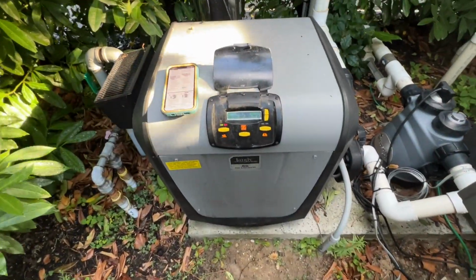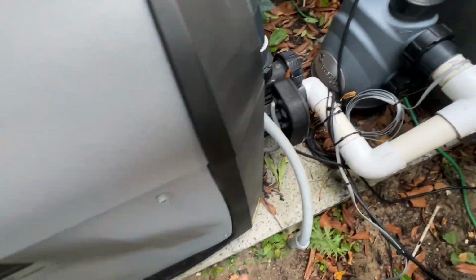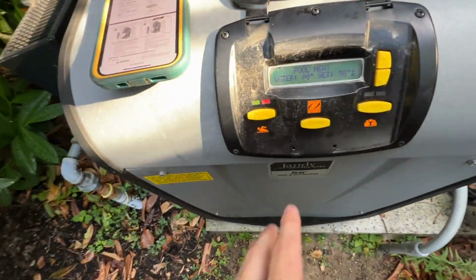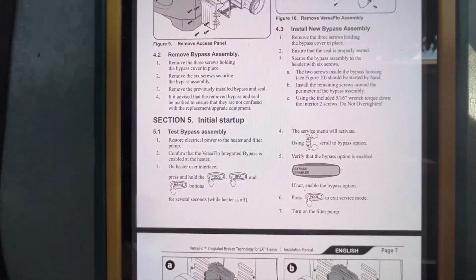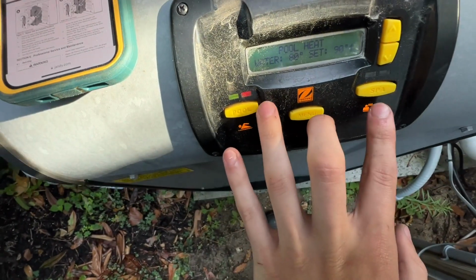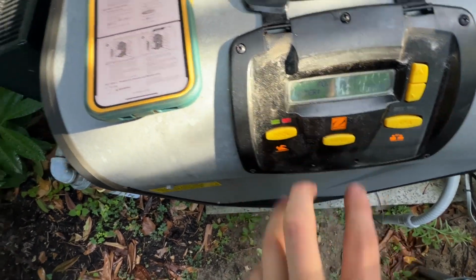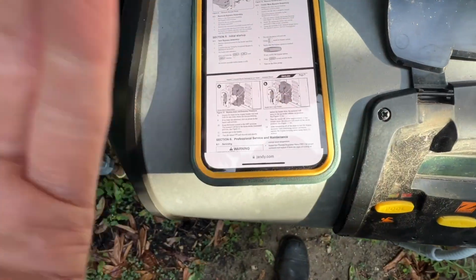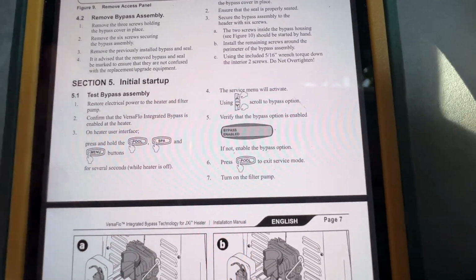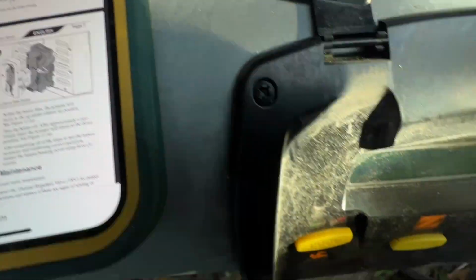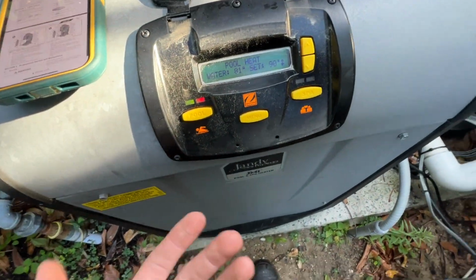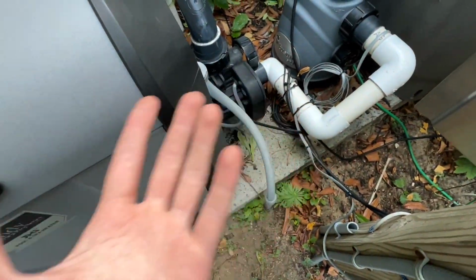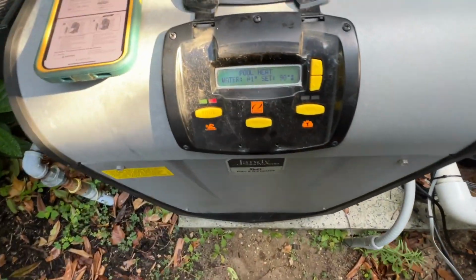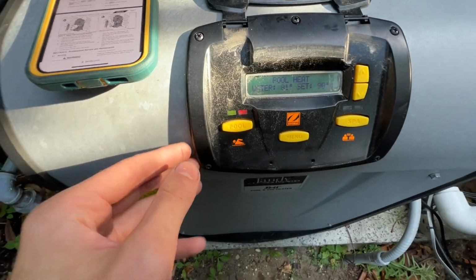And the final thing I did have to do, once I got the cover on, was enable that VersaFlo Bypass. I followed these instructions here, which is while it's off, press and hold these 3 buttons for 7 seconds, and you can scroll through the menu to get to the bypass option and make sure that's enabled. I did hear the valve open and close when it was off and then when it was on, so it is working.